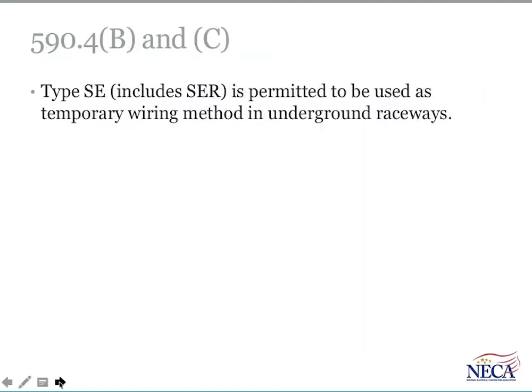Moving out of healthcare facilities, Article 590 provides rules for temporary power and temporary construction power and so forth. There's a small change to actually align with common practices in the field to allow Type SE cable, which includes Type SER as well, permitted to be used as a temporary wiring method in underground raceways.